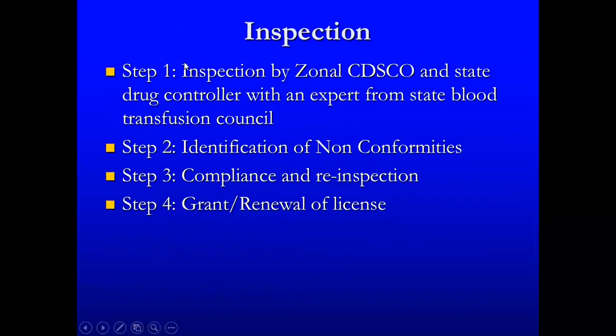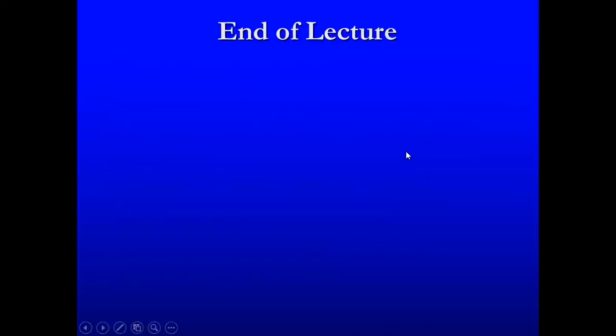The steps for obtaining a license are: first, joint inspection by CDSCO and the State Drug Controller along with an expert from the State Blood Transfusion Council. Second, identification of non-conformities by the team of experts during the inspection. Third, the blood bank submits compliance and a re-inspection is done. Finally, after compliance submission, there is grant or renewal of the blood bank license. Thank you very much.